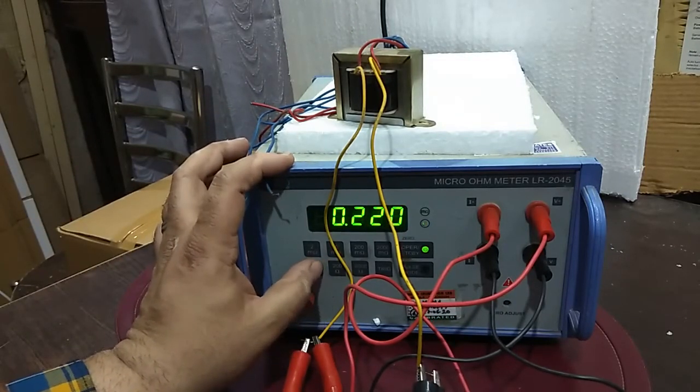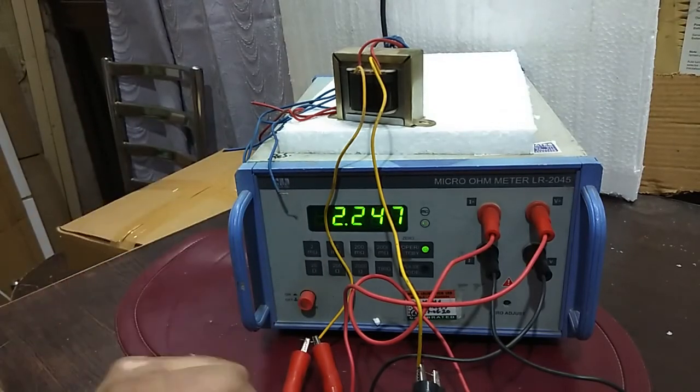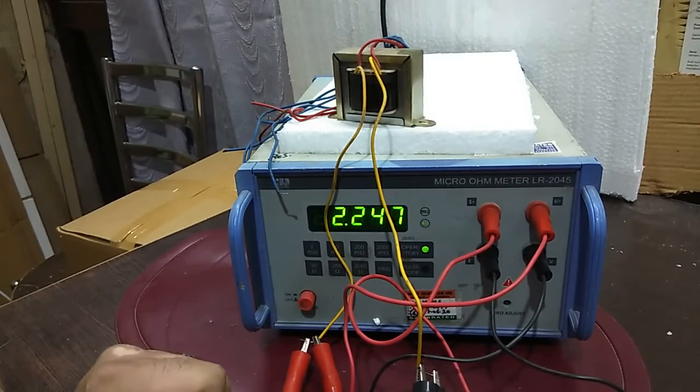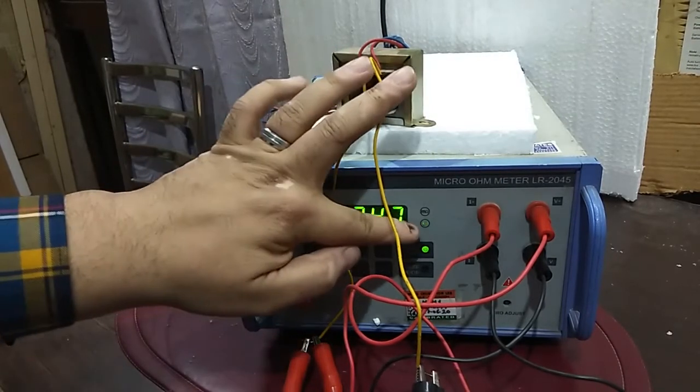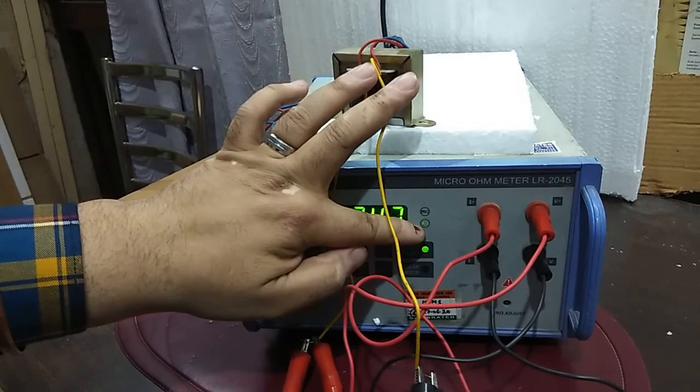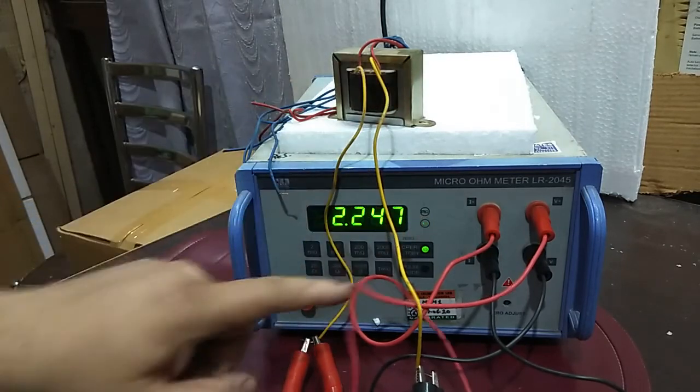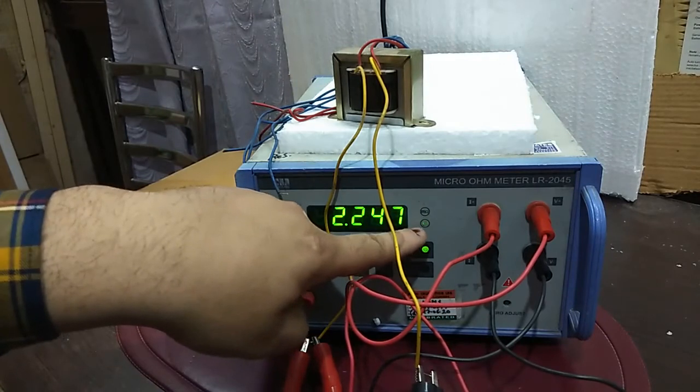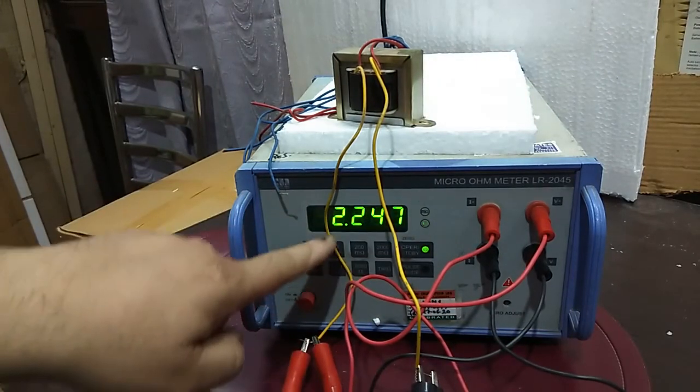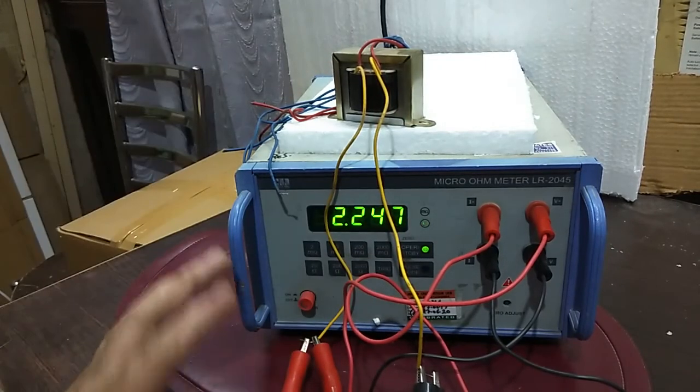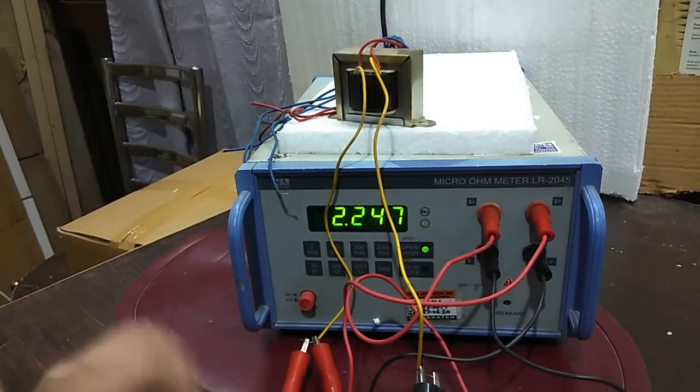It's showing 2.247 ohm. See the light is also over here. If the results will be in milliohm then this light will be on. Now this light is going on means it is ohm. So the results of this transformer is 2.247 ohms.